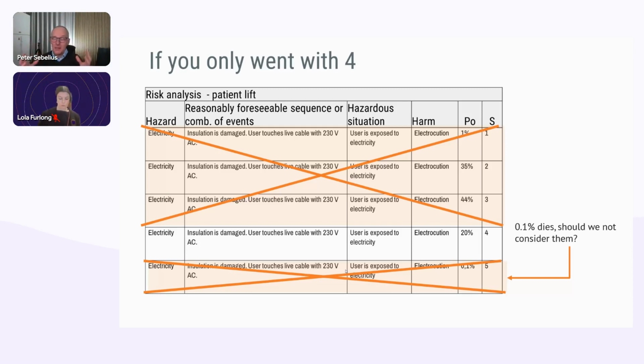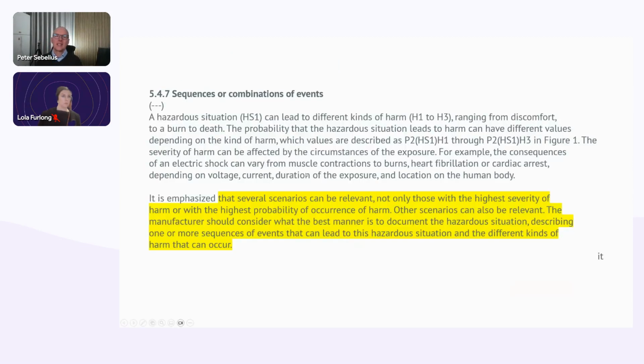Now, this might be a little bit terrifying. You can see yourself expanding your risk tables here by a factor of 5 if you include all harms and severities for all risks. Am I just making life difficult for you now? Or is there any support for this in the standards? And actually there is. If you take a look in the ISO/TR 24971, I know it's not the standard, but it's sort of a very trustworthy guidance. And you can see here what it says.